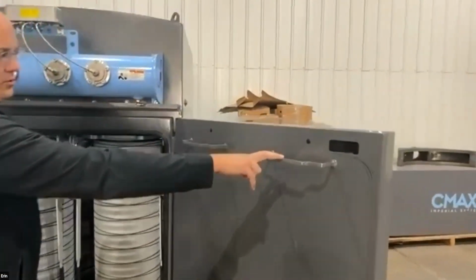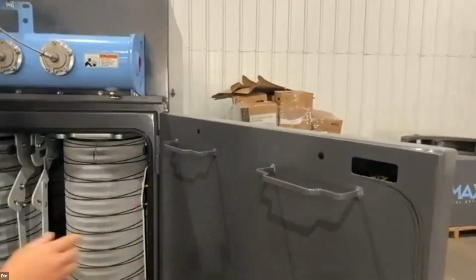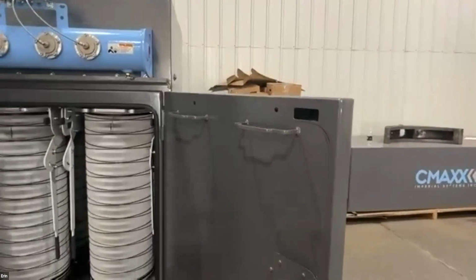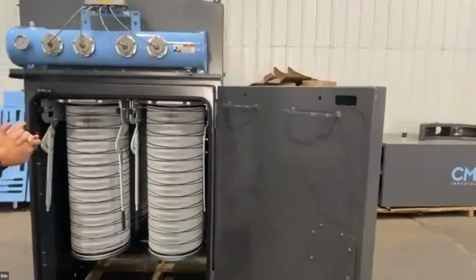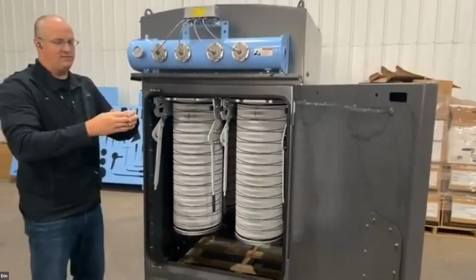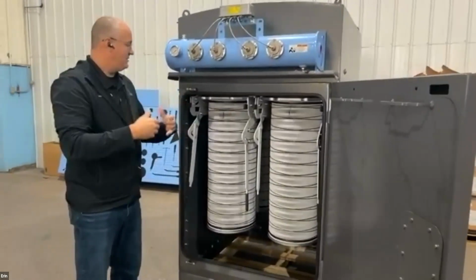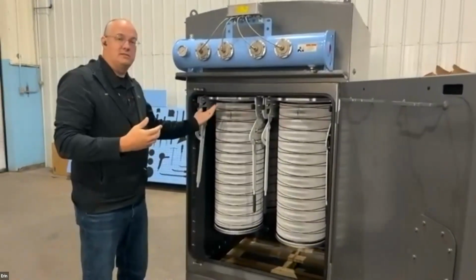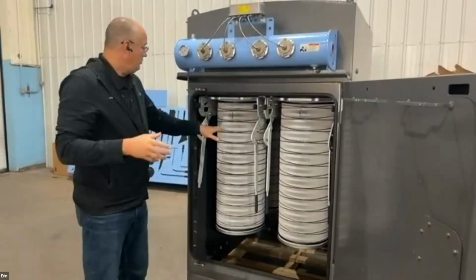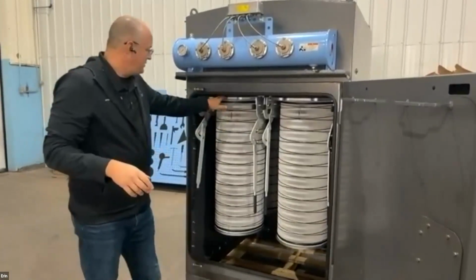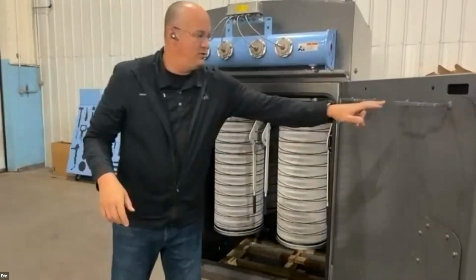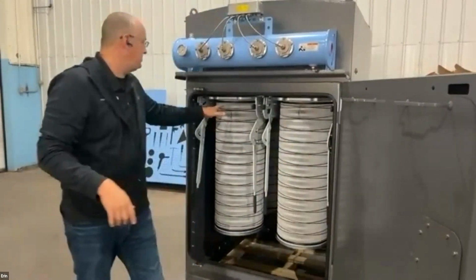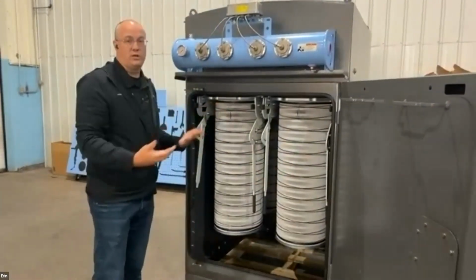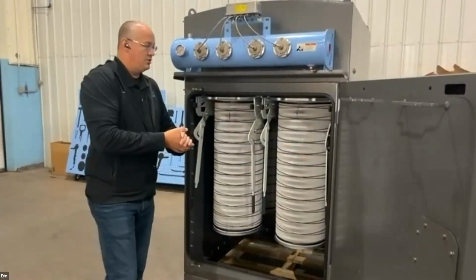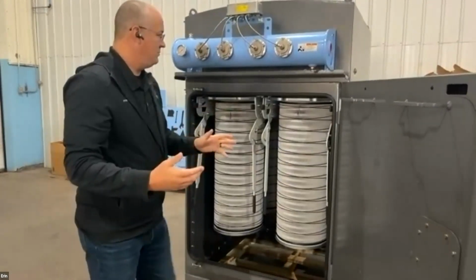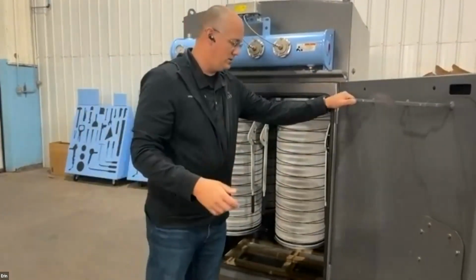And this also, at times, people may not push the filter in all the way, engage it into its proper position, and that leaves the hole on the top. It leaves a gap, and air and dust and dirt can get by on that. So what we've done is we've built this pan in such a way that if it's not engaged in the correct place, the door cannot close. So those are just a couple safety features and benefits that are to ours.